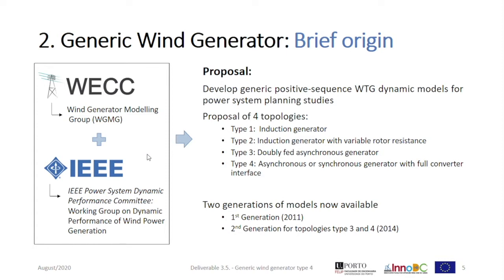They came up with a proposal of four topologies: Type 1, induction generator; Type 2, induction generator with variable rotor resistance; Type 3, doubly fed asynchronous generator; and Type 4, a synchronous or asynchronous generator with full converter interface.